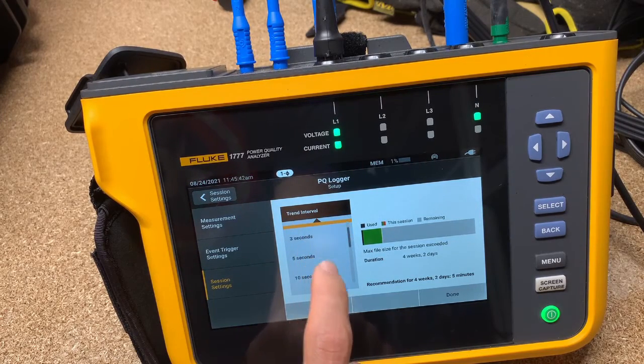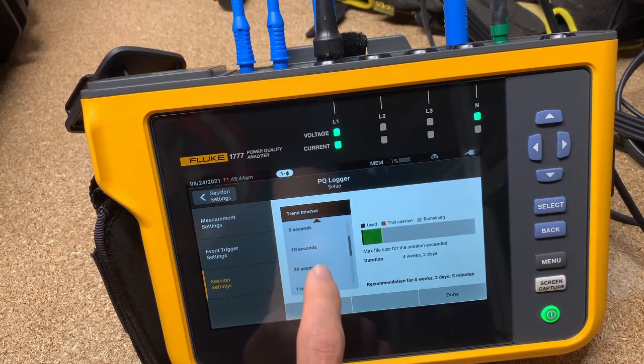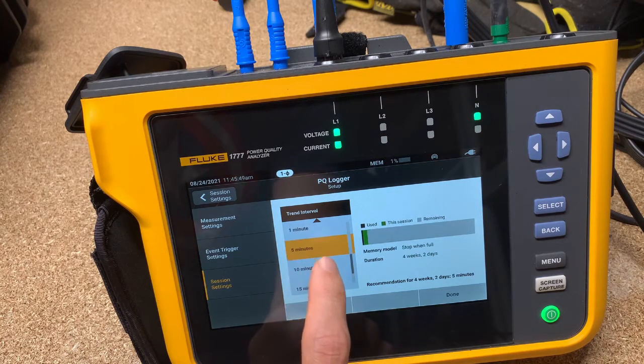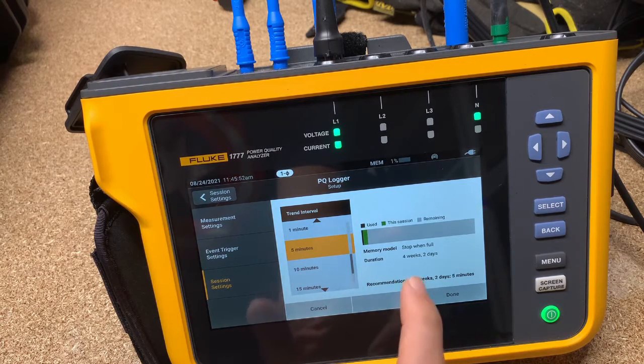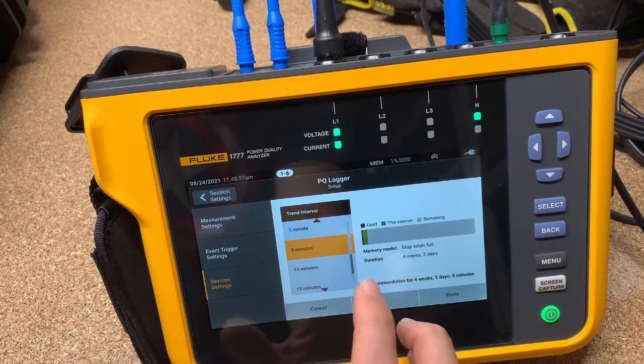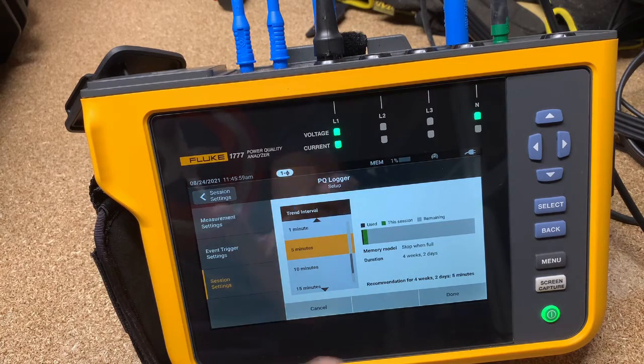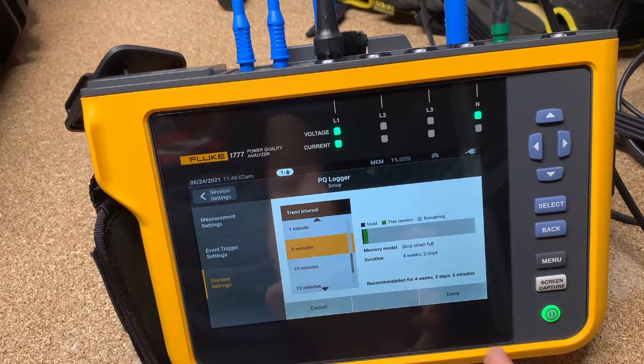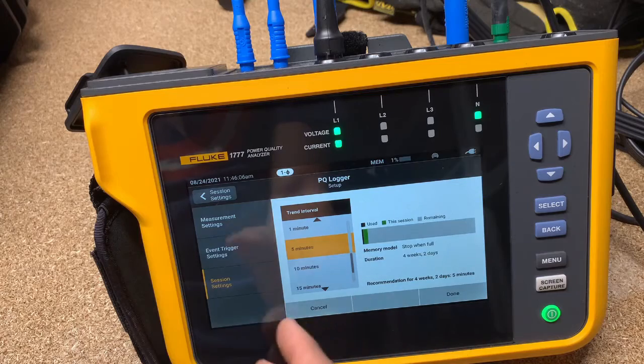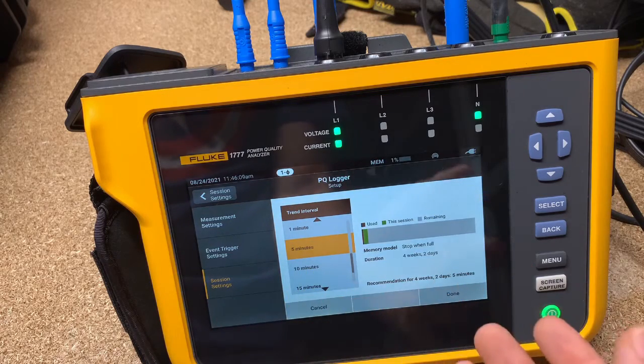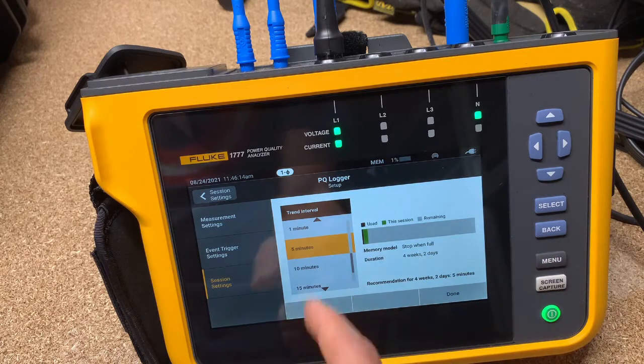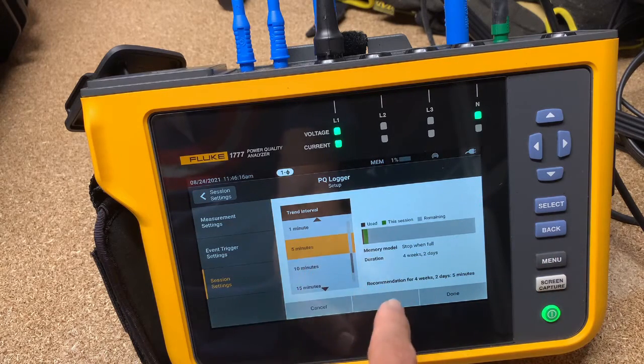Just because we're averaging once per second — getting the min, max, and average once per second — doesn't mean we're going to get more or better data than if we did every five minutes. The reason is, during those five minutes we're still recording and logging everything, and at the end of the five minutes we're recording min, max, and average. So you're not going to miss anything for min and max. If there are multiple events that occur at minute one, minute three, and minute four, all of those events will be captured.